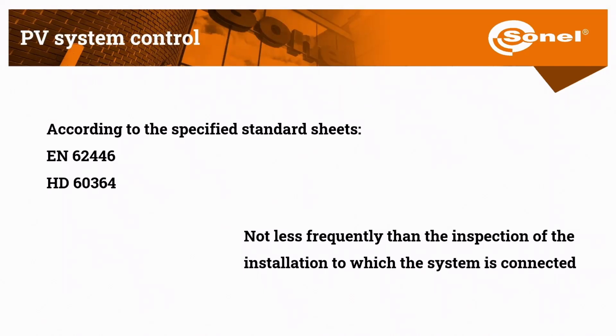The standard also forces us to do the survey at the very beginning, but also to make measurements after some time. It depends where the installation is placed. Some countries and some regions request a service not more than 5 years after the installation, and some big customers, for example factories that have an installation on site, force through ISO standards to make that kind of measurement every year or every 2 years.